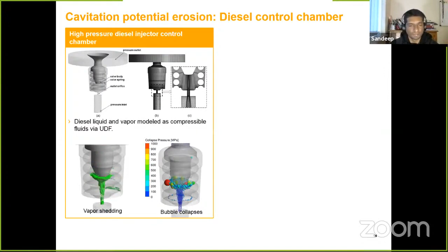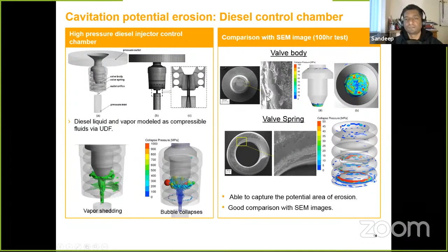Vapor formation happens in the orifice, but the collapse of the bubble happens somewhere else, and the erosion is happening somewhere else. You can see inside this there is a spring in the control chamber. The spring gets eroded, the spring is getting damaged. That is all captured in the CFD simulation. You can see these are all the high pressure regions where the spring is getting damaged. And on the control valve body, only the tip of the valve body gets eroded. You can also see that from the electron microscope image. So this is something which is now tested and proved.